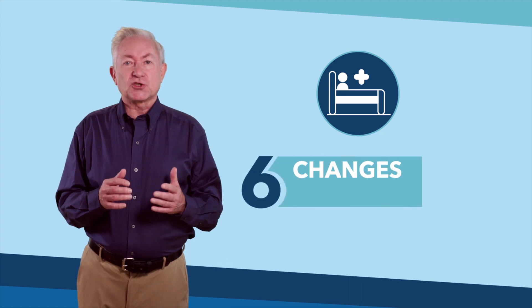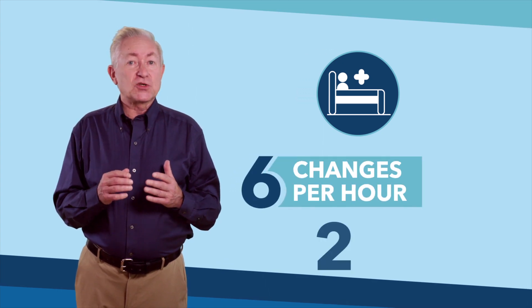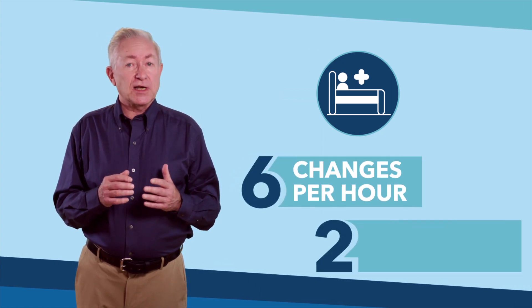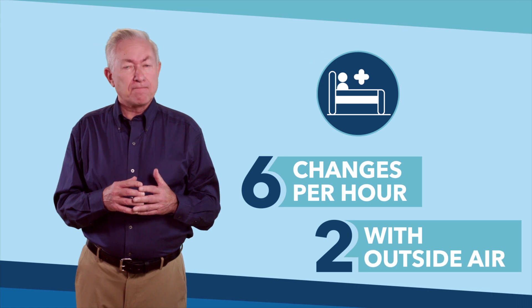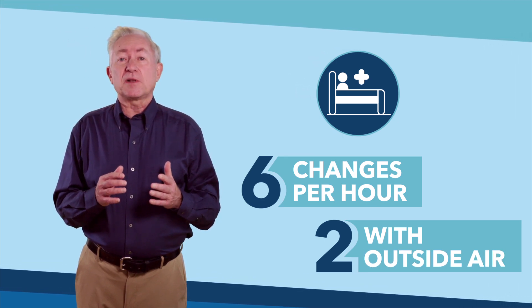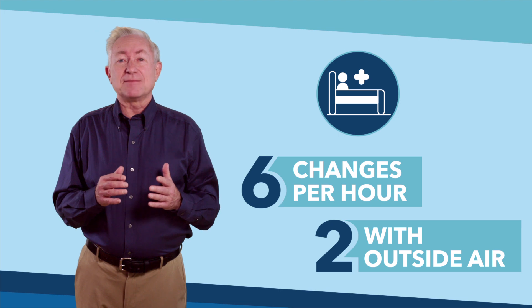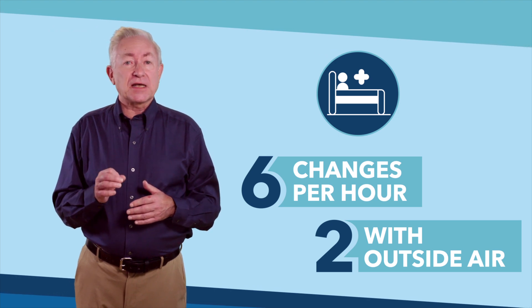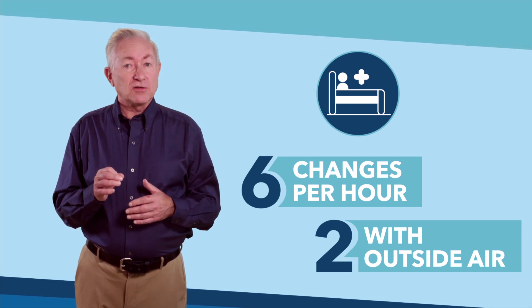There are building codes that set the minimum requirement of outside air being brought in based on the type of space. For example, a standard patient room has to have a total of six air changes per hour and at least two of those air changes have to be with outside air. This means that the total air in the room has to be fully replaced six times each hour and 33 percent of that air must be fresh air from the outside.